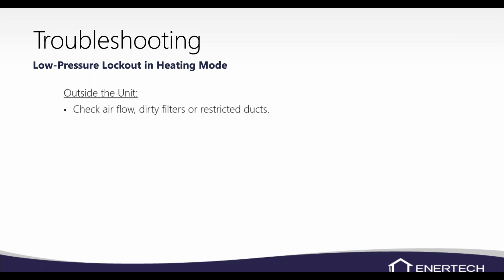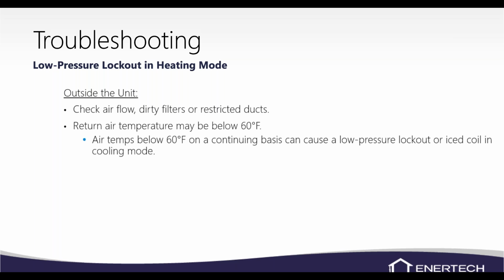Low pressure in cooling mode, should be cooling mode here. I apologize, it says heating mode. Because low pressure in cooling mode, we're going to look at the air side or the load side of the unit. So outside the unit, obviously dirty air filters, airflow issue. You know, you've got a blower that's not operating, it's spinning backwards, something like that. Restricted ductwork, zoning issues, return air temperature is too low.